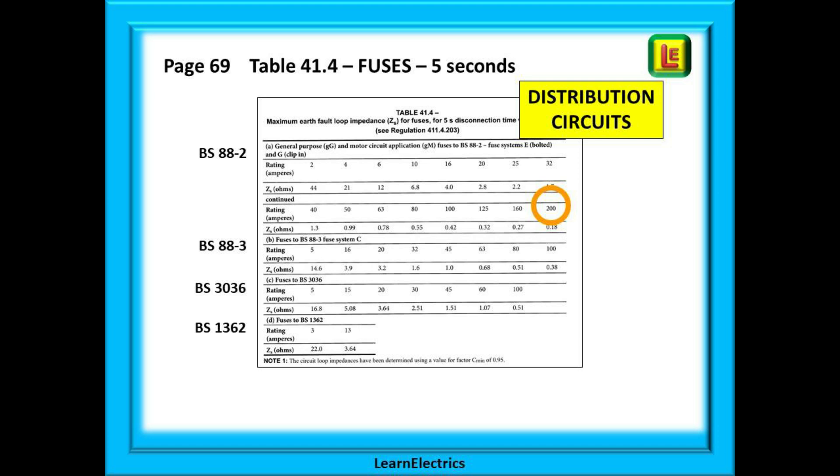Moving on to page 69, we find table 41.4, the table for fuses with a 5 second disconnection time for distribution circuits. There are four types of fuse as before. But notice in the orange circle, the fuse sizes now exceed 63 amps. Because this is a distribution circuit. And this one is showing 200 amps.